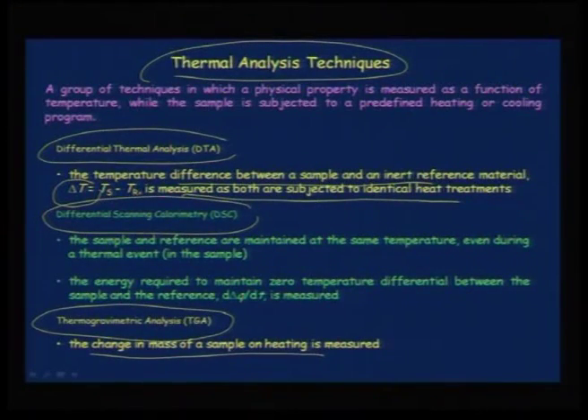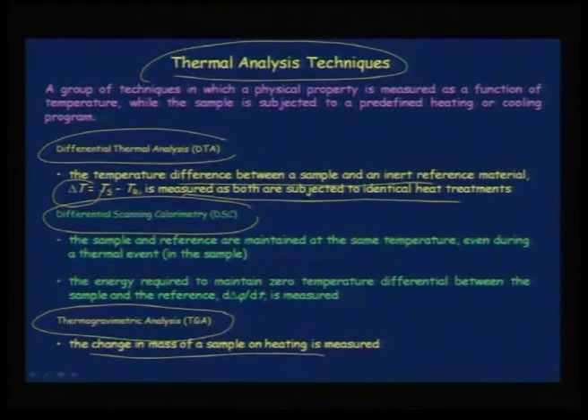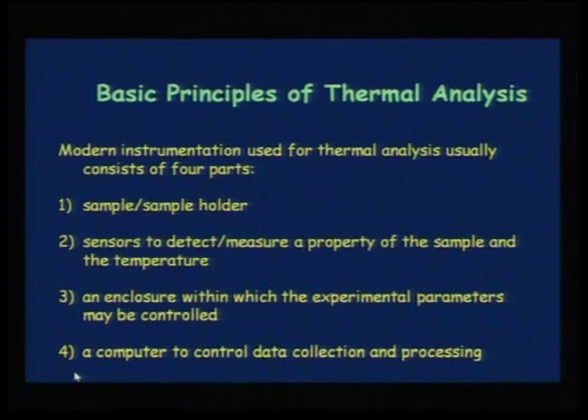In DSC, this is not the temperature difference between sample and reference — it is the heat flow, whether taken by or given out by the system, because we maintain both at the same temperature. In thermogravimetric analysis, it is merely a change in the mass of the sample on heating. DSC gives a more quantifying picture, DTA is more qualitative, and TGA is a very different analysis altogether.